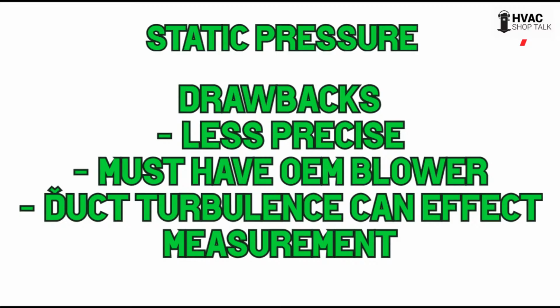Static pressure has another drawback: duct turbulence can affect measurement. If you get a really odd static pressure reading, like you plug something in on a big system expecting some resistance and suddenly it's really low, move the probe and try again in a different spot to see if that was the issue. I've had some duct systems, especially pressure plenums, that don't have real linear flow.